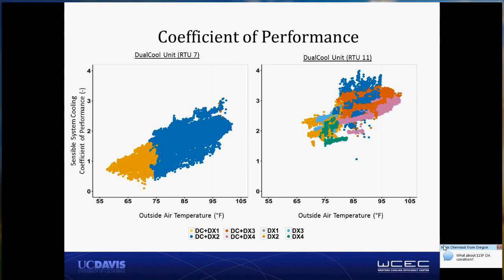We found that the airflow rate for a lot of these systems is far lower than it should be. There's issues with economizer operation and issues with charge for the refrigerant systems. Now, all of that is about the baseline equipment. It's not a problem with the dual cool equipment, but it does cause performance to suffer. These you see are two different dual cool systems with significantly different coefficients of performance because of the baseline equipment to which they're added.